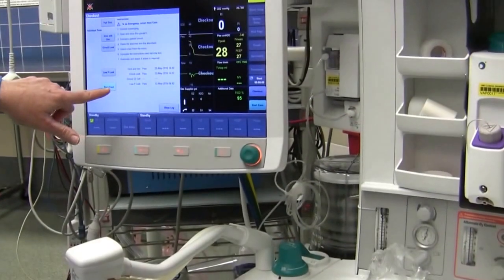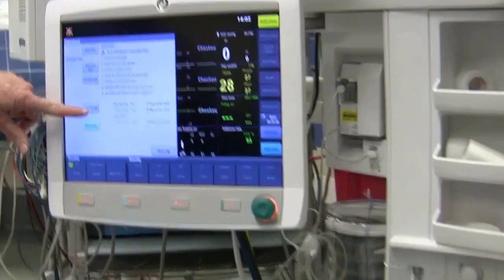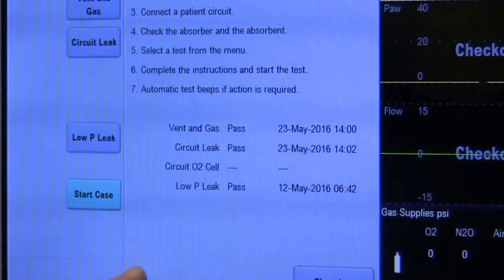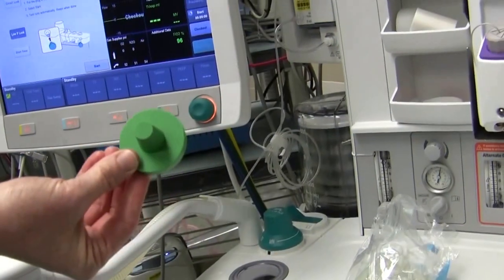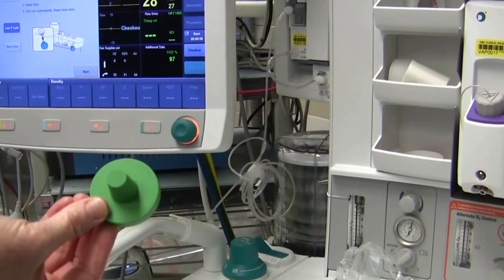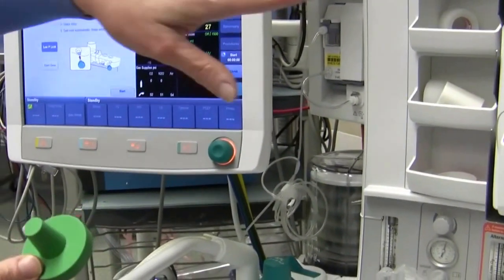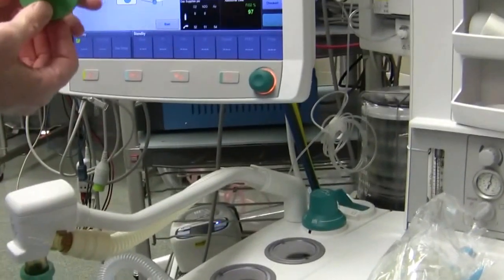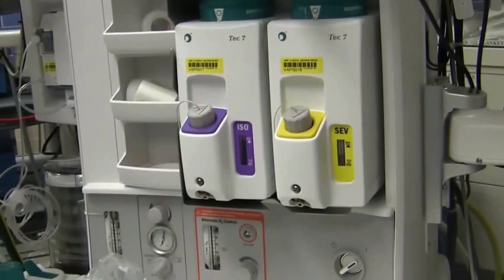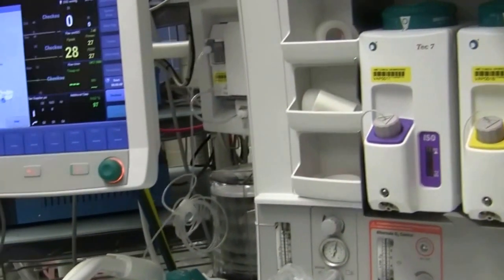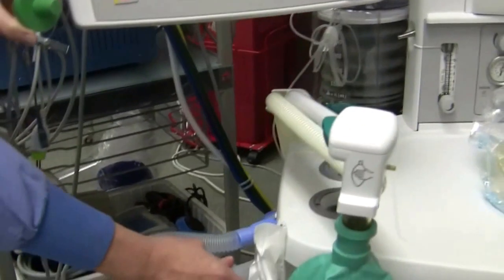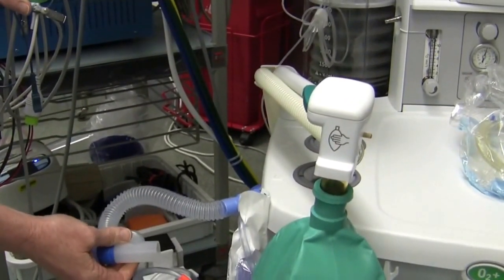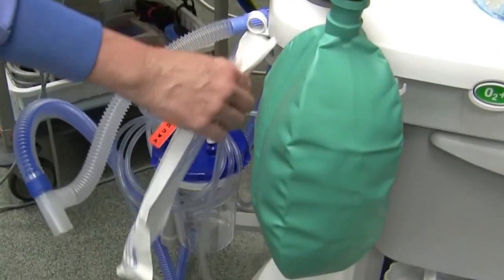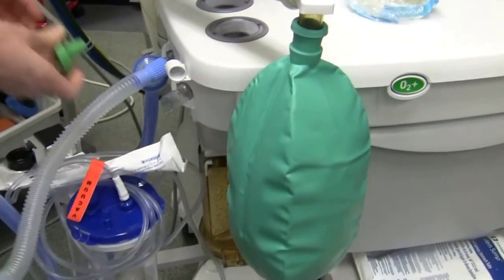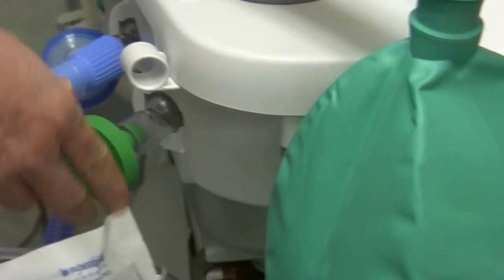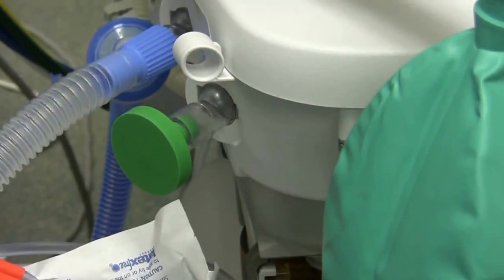If we go back to the beginning one, we also can do our low pressure leak. I did that by hitting the back. And you run this 3 times. You want to run it with the vaporizers closed, and then you run it 1 time with each vaporizer open. So what you do is they want you to take this plug and put it in the right hand port. You plug the port. I have my vaporizers closed, and I hit start.